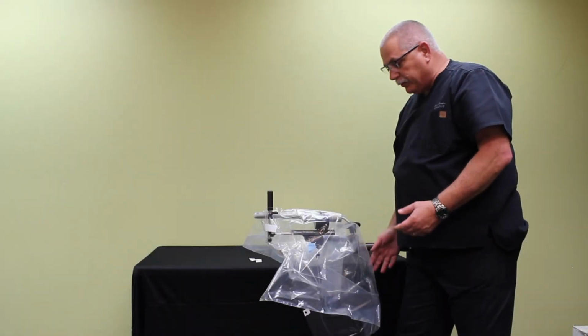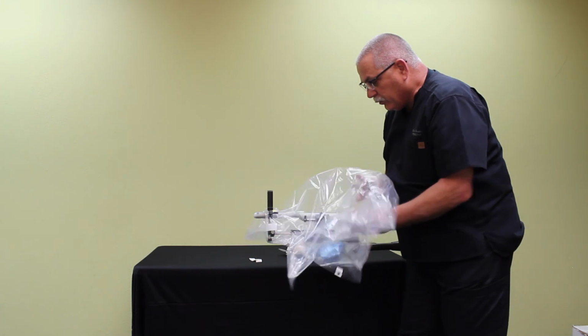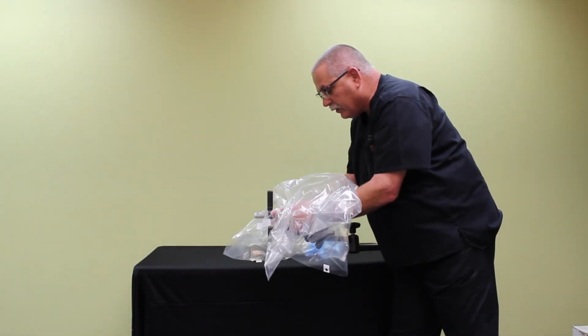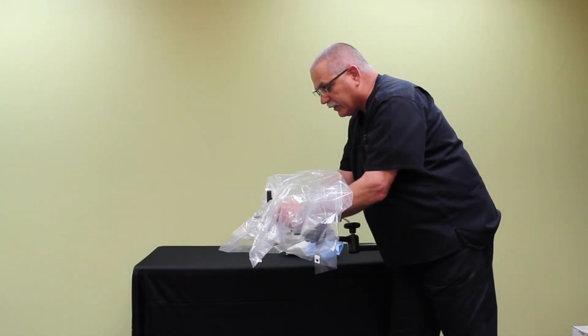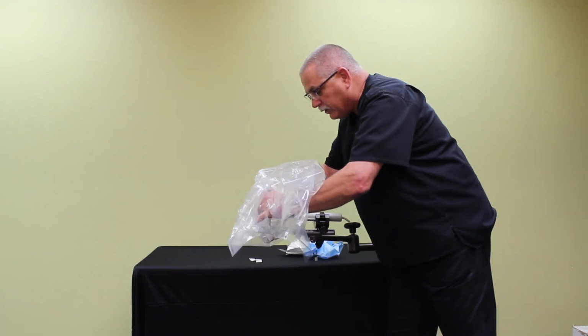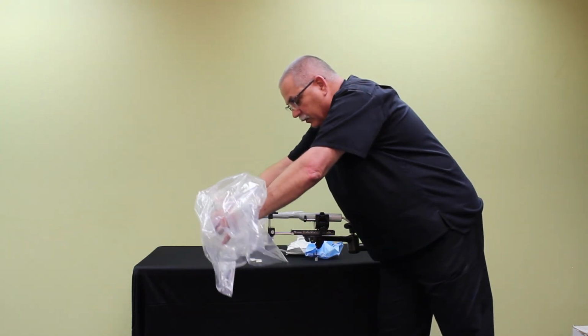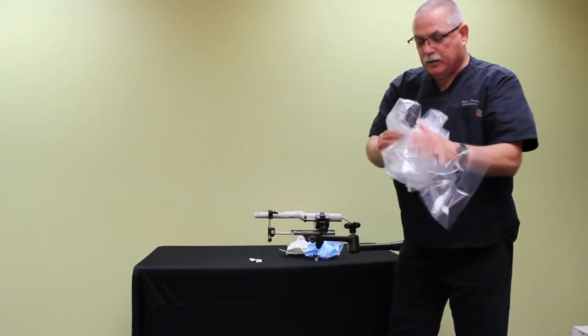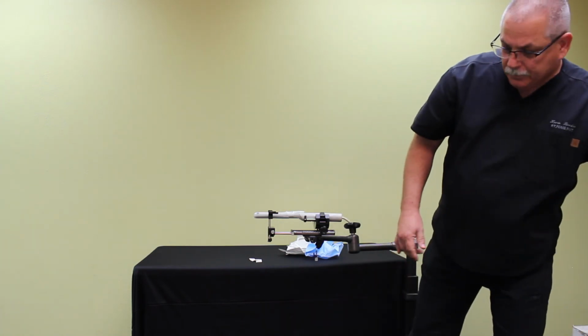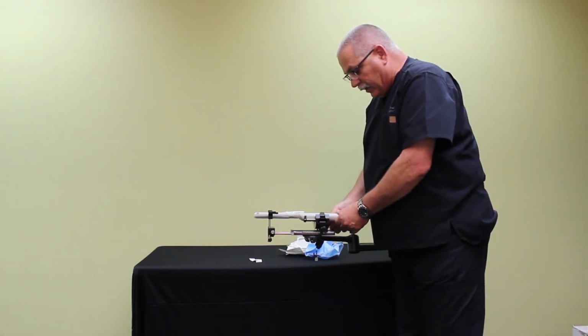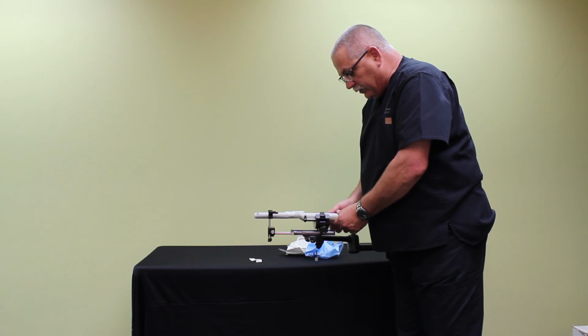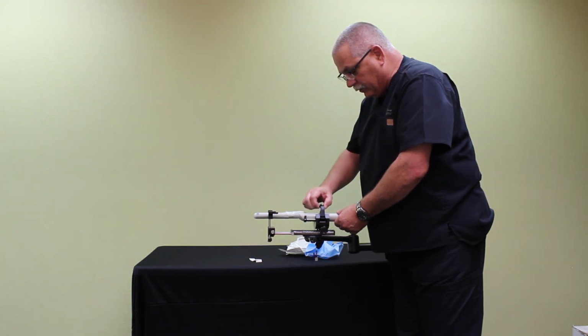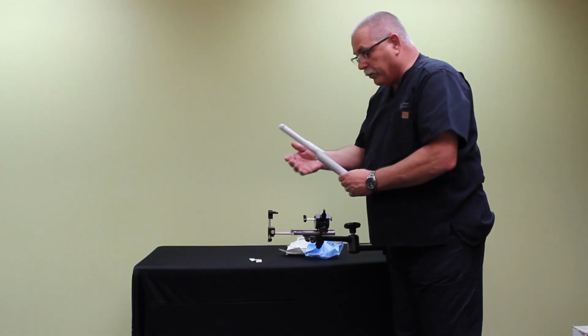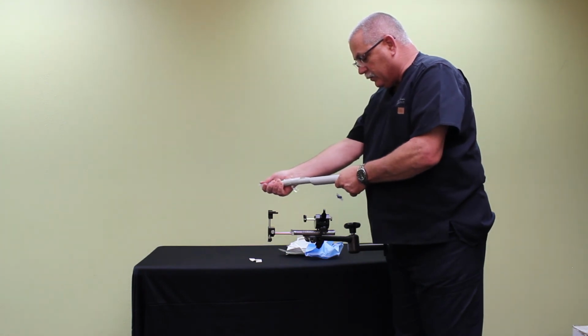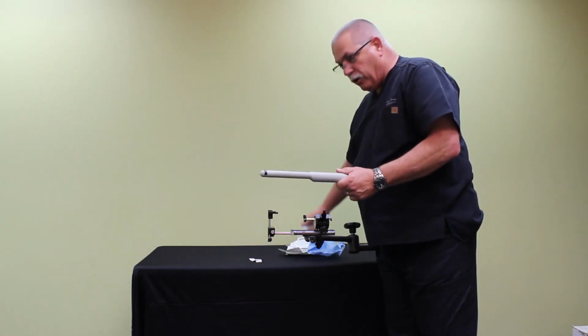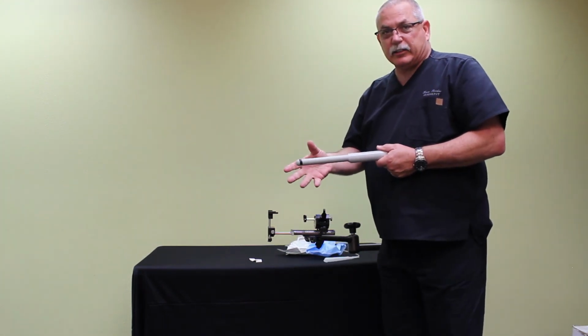Once the procedure is completed, reach under the drape, unlock the grid. Because the drape and the grid are disposable, I'm going to take them off and dispose of them properly. Then I'll take the probe out of the cradle, remove the cover, and send the probe off to be first cleaned and then high-level disinfected.